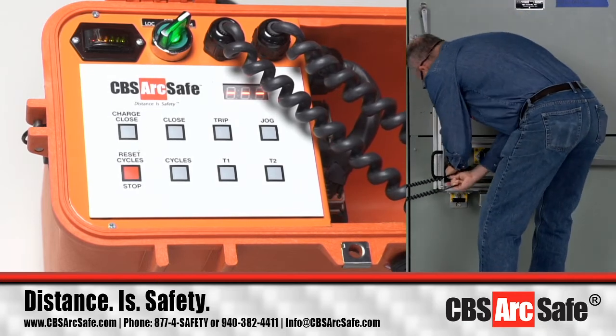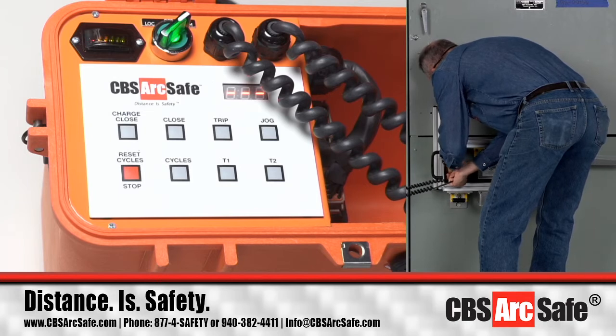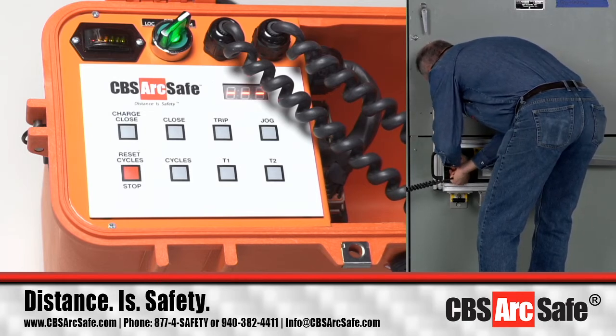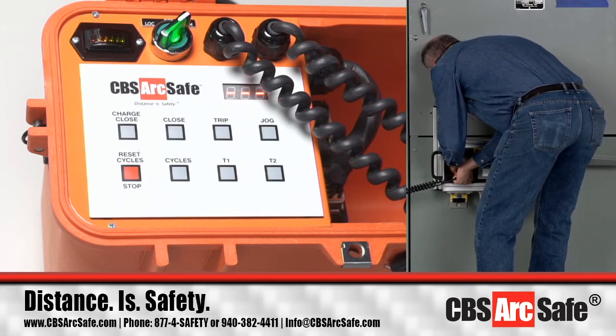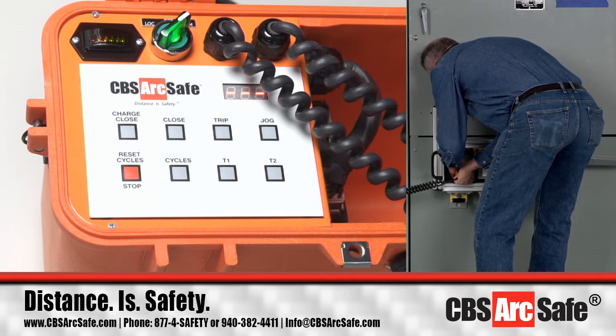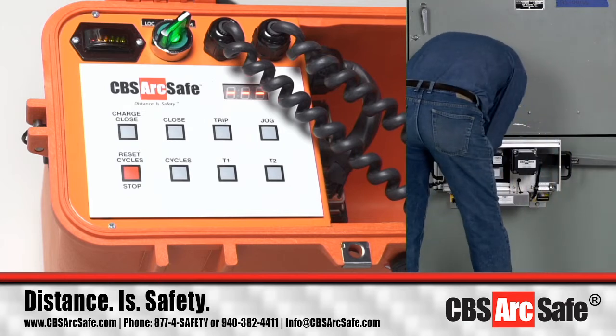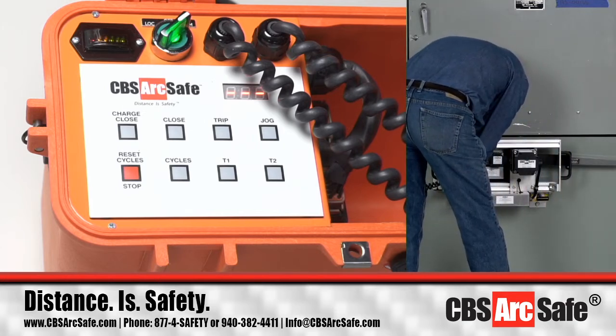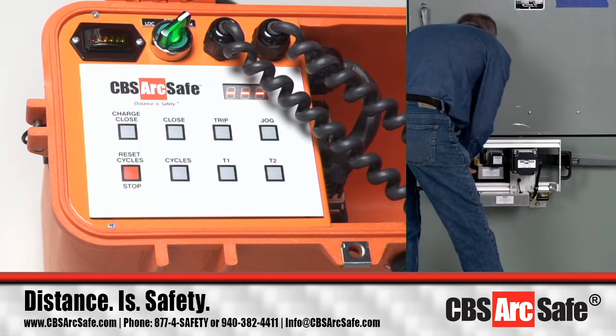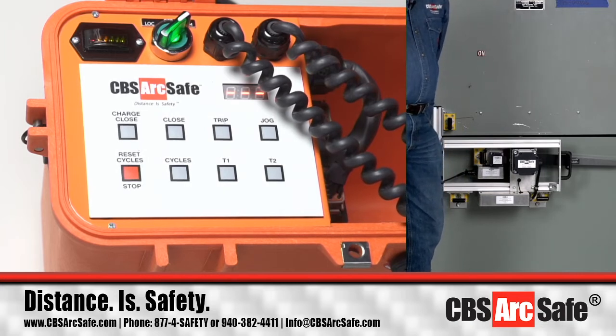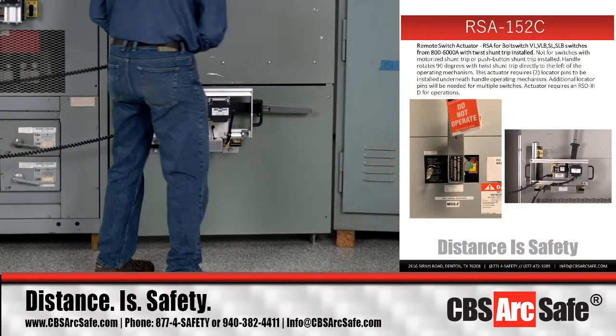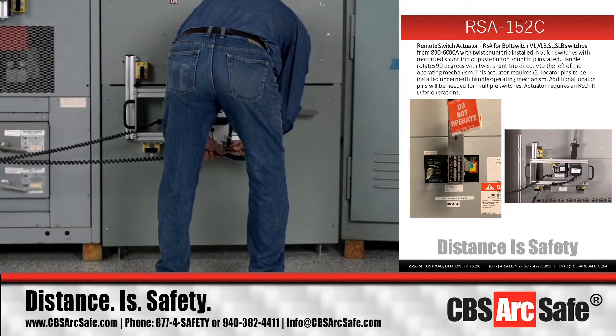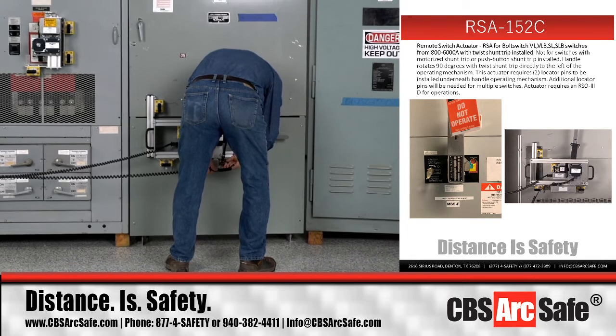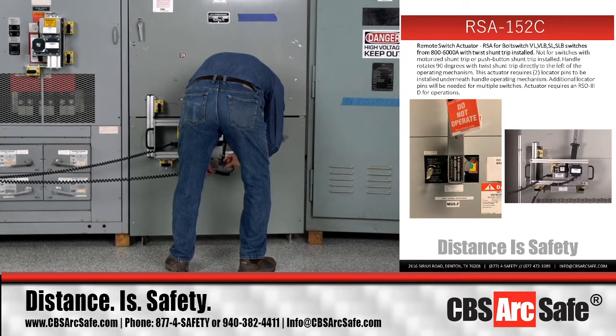You may talk about the different angles of travel with the bolt switches, twist shunt trip. The bolt switch actually comes in a variety of different operations. With a Pringle switch you have 90 degrees of travel up and down, or 115 degrees of travel for close. The bolt switch has its own unique characteristics, whether you've got the VL, the SB, or the BL switches, and we work to know exactly which type you've got so we know the proper geometry you're needing to work with.